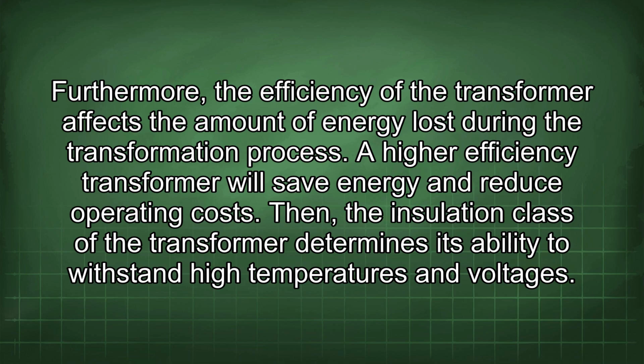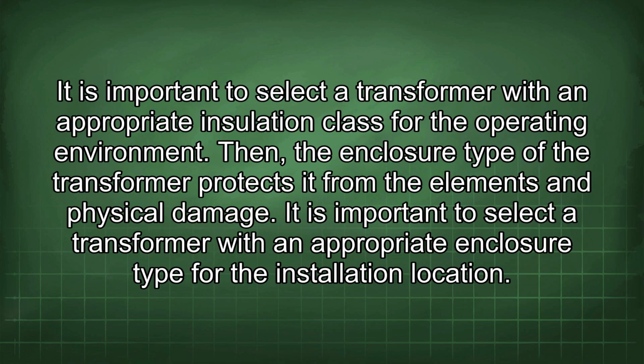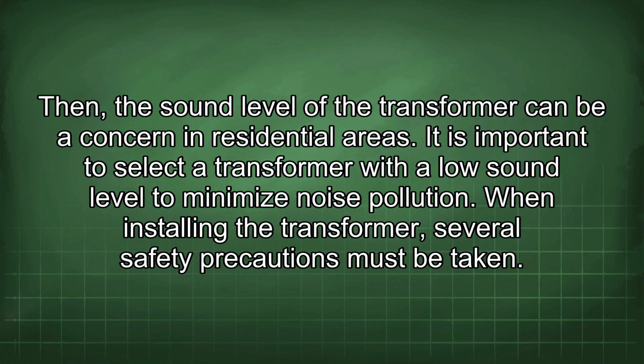Then, the insulation class of the transformer determines its ability to withstand high temperatures and voltages. It is important to select a transformer with an appropriate insulation class for the operating environment. Then, the enclosure type of the transformer protects it from the elements and physical damage. It is important to select a transformer with an appropriate enclosure type for the installation location. Then, the sound level of the transformer can be a concern in residential areas. It is important to select a transformer with a low sound level to minimize noise pollution.